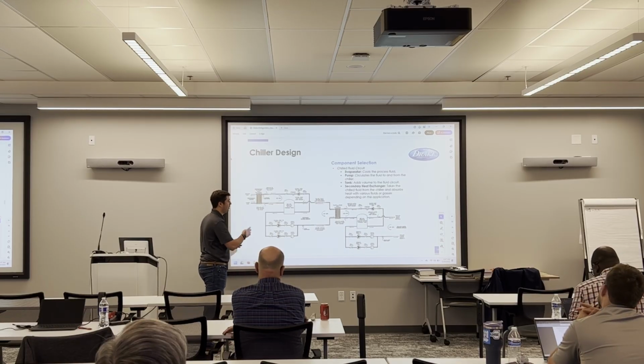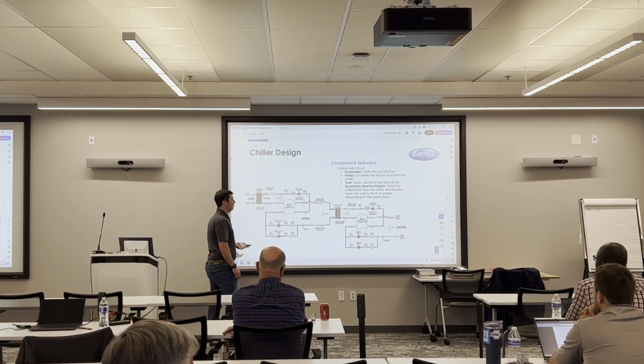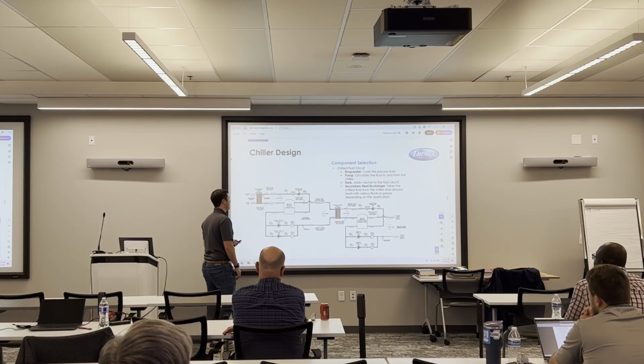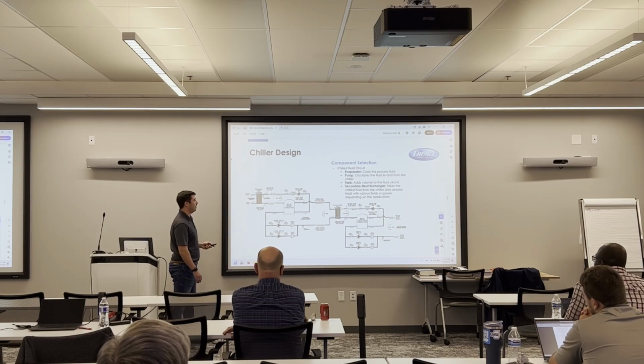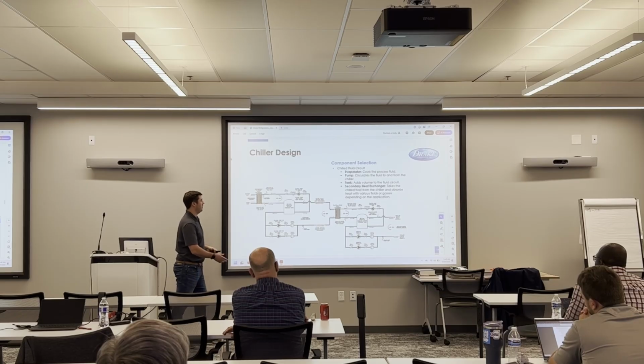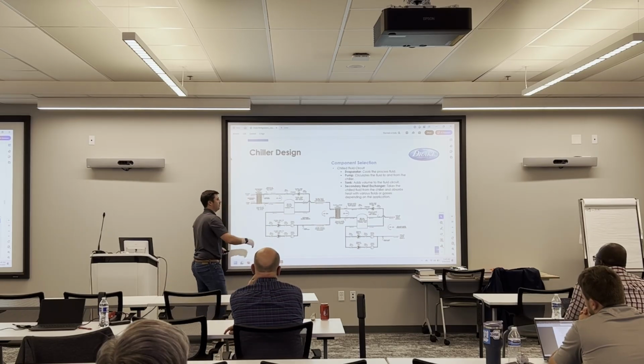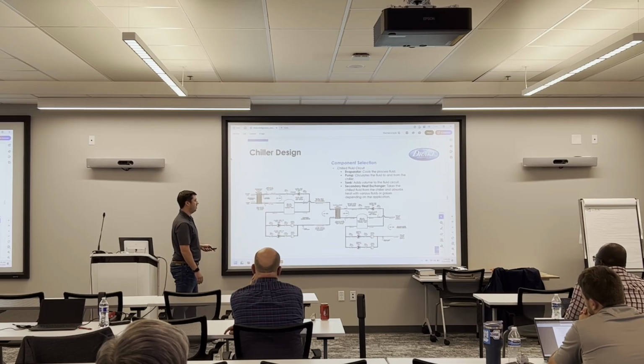And then on the secondary process loop, we'll say this is water on this side. Maybe the customer wants to maintain 40-degree water in this tank. And if that's the case, we probably want to maintain about 30-degree glycol over here, just so we have some heat transfer there. So they'll have a separate pump pulling off the water tank at 40 degrees, or we'll say 50 degrees. It comes into the secondary heat exchanger, and it's going to leave colder and go back to the tank. So very similar to this recirculation loop, just on a water cycle. And then same thing down below. We have a set of process pumps pulling off the tank. You go into your customer's process loop, whatever that may be.